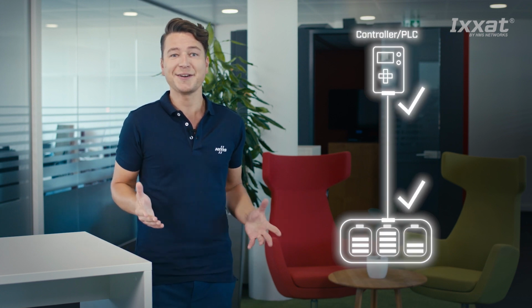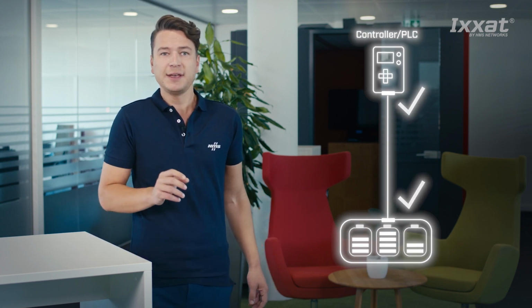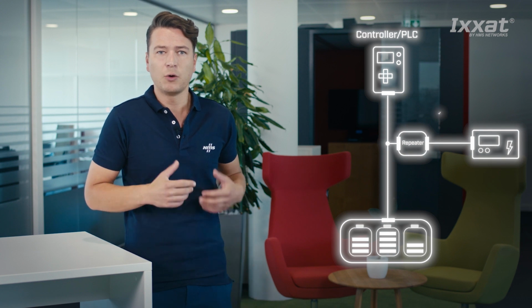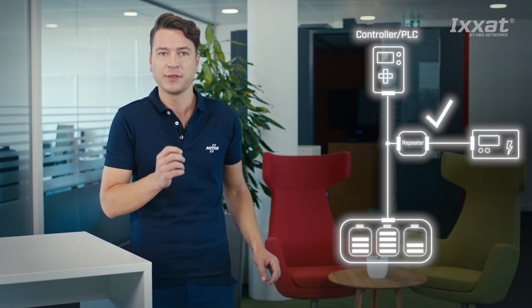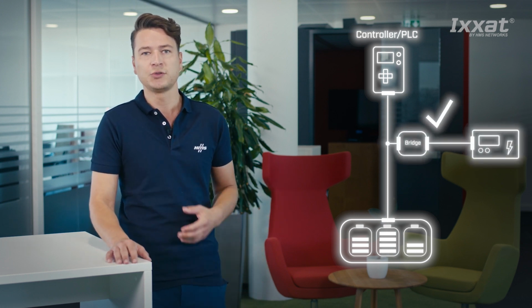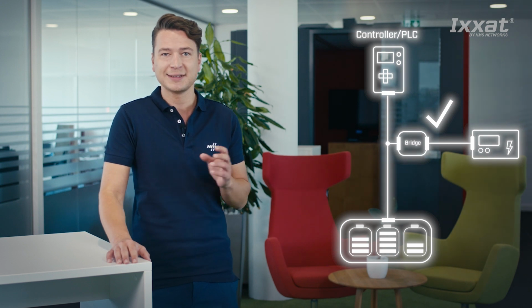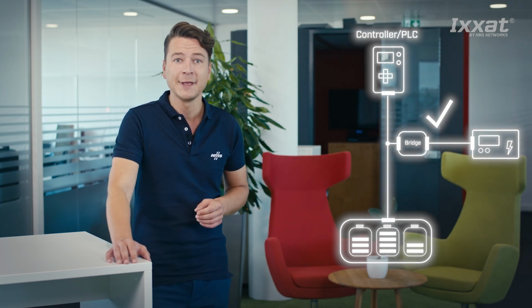But how can you protect your system? Galvanic isolation is the key here for you. This is achieved either by using devices that are already galvanically isolated with special interfaces, or by using repeaters or bridges with built-in galvanic isolation to divide the system into isolated subsegments. This protects BESS components from overvoltage and prevents electromagnetic influences from spreading across the entire network.